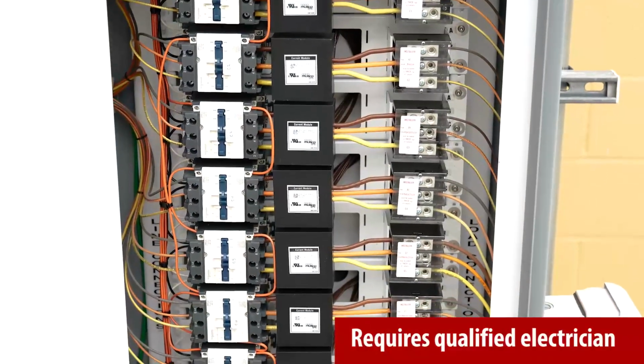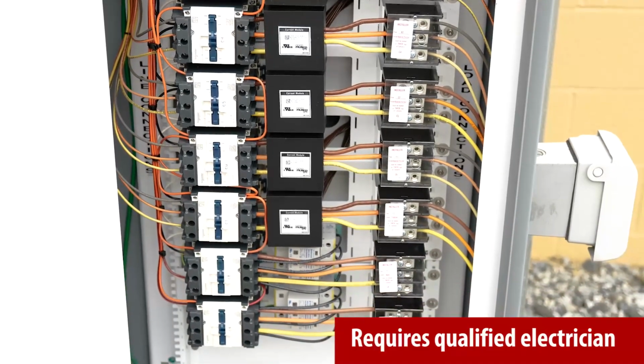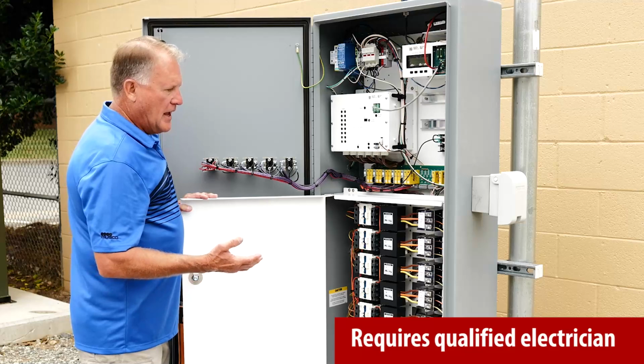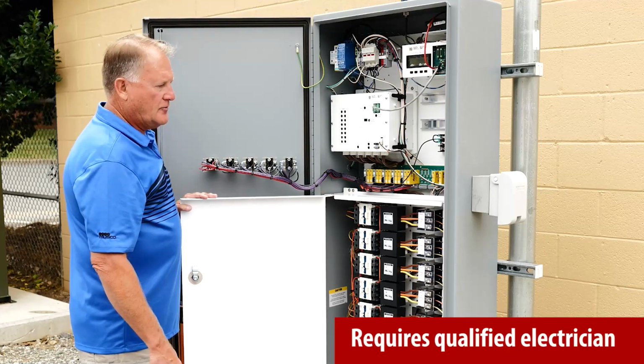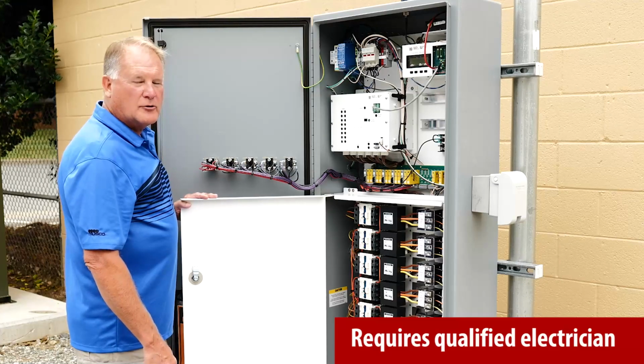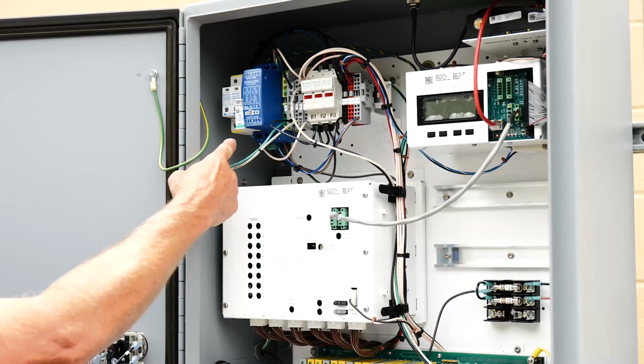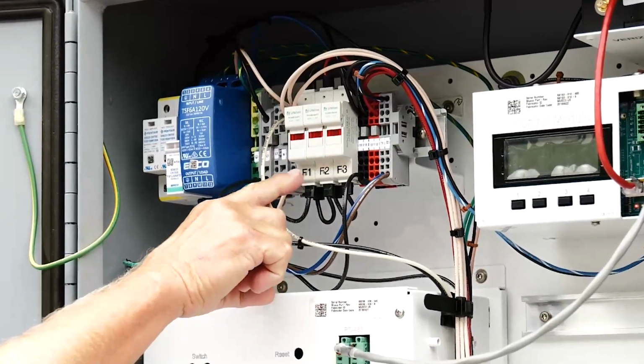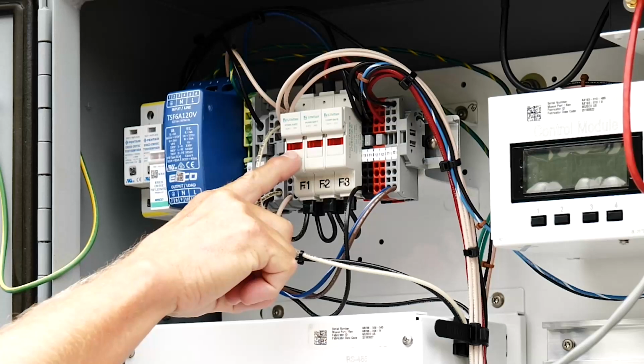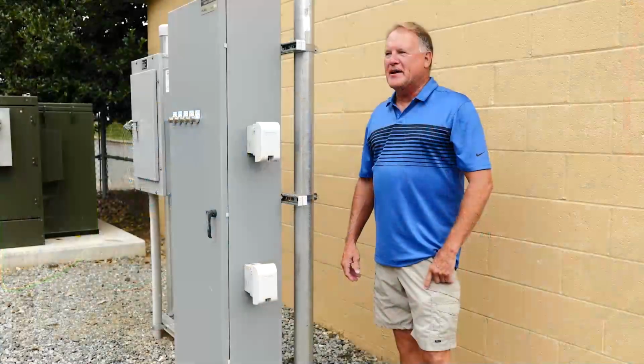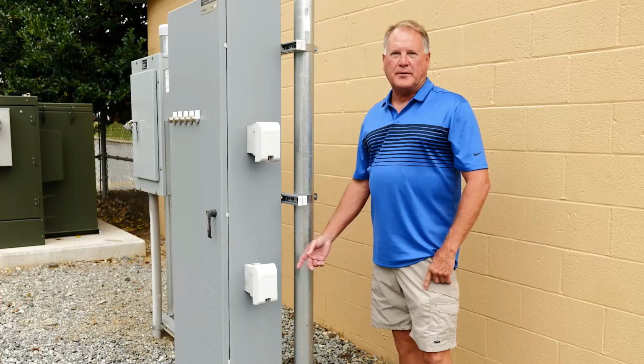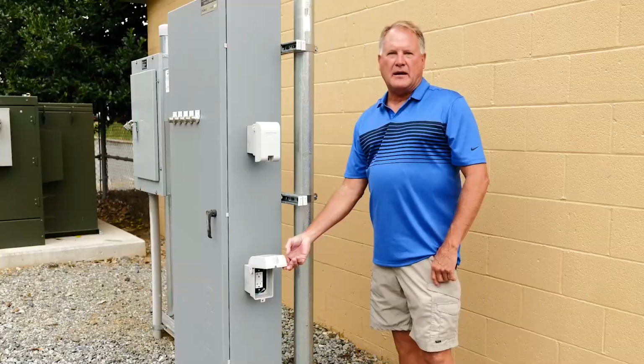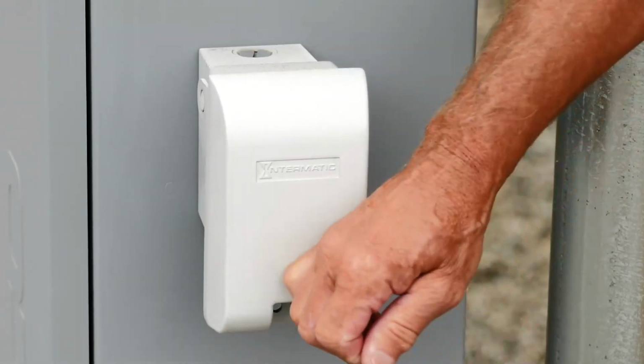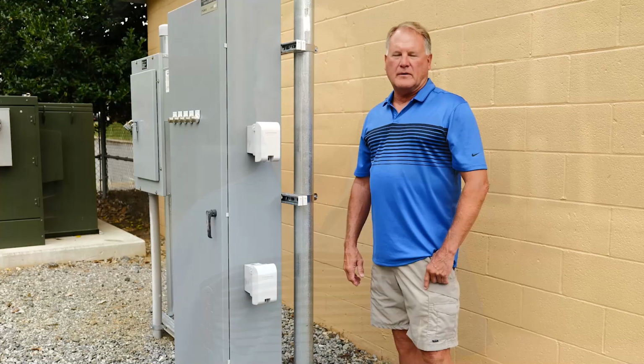Arc flash warning. Everything is neatly secured, wired, and in place so that you don't have potential for damaged wiring or excess stress on terminal points that could cause loose connections and heating of the wire. A well-designed control system will have internal surge protection as well as fusing. This system has a red window that will illuminate in the event of a blown fuse. If your service is located outdoors and has a receptacle on it, it should be GFCI rated and weather rated, and also have a heavy-duty, non-accessible cover. Fuses are an important part of your lighting system safety.